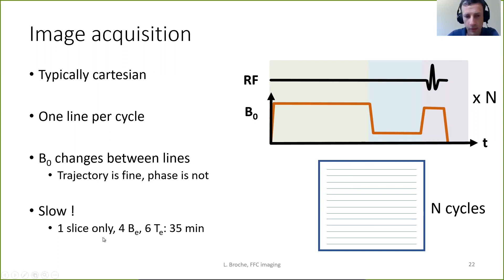And of course, as I said, we have a problem with temporal stability because the field that we have for each acquisition of the line is slightly different. That's because the current is not exactly the same. In order to avoid problems, we need a current stability and shot-by-shot reproducibility of below 1 ppm. At the moment, it's about 10 times bigger. So the image looks like this, as you can see. Instead of having a nice dot, this was a bottle phantom, it tends to blur like this.